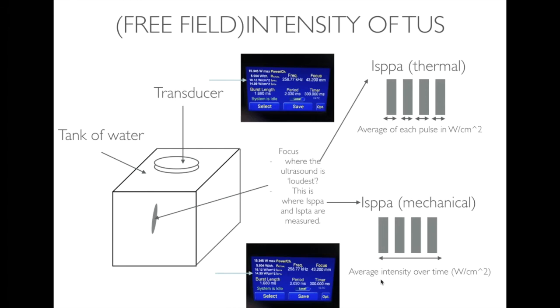We've also got the ISPTA, which stands for Spatial Peak Temporal Average. That is the average intensity measured within a medium like the water tank, averaged over time, rather than simply averaged across pulses. If you're good at maths, you'll figure out that the ISPTA has a bigger denominator than the ISPPA, which means the ISPTA is usually lower than the ISPPA.